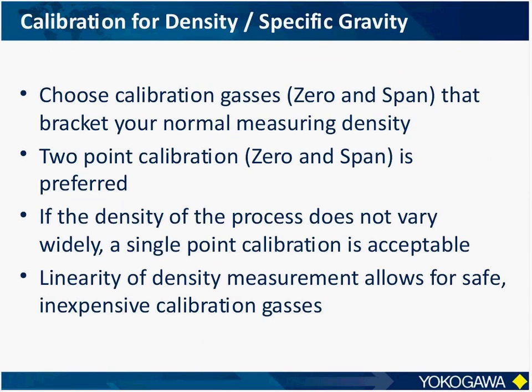When we're doing calibrations for these density or specific gravity applications, we simply want to choose calibration gases that bracket your normal measuring density. A 2-point calibration, a 0 and a span, is preferred. However, if the density of the process does not vary widely, it is acceptable to choose a single-point calibration. You want the calibration gas to have a density very close to your process density. And once again, the linearity of the measurement allows for safe and inexpensive off-the-shelf calibration gases.